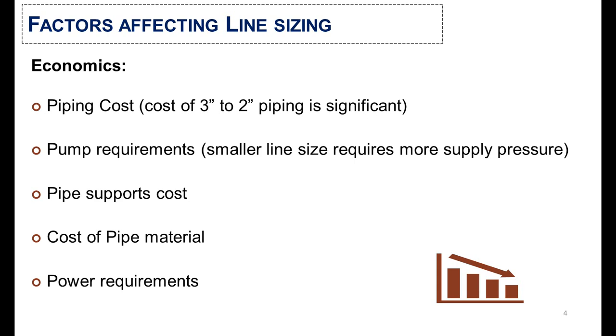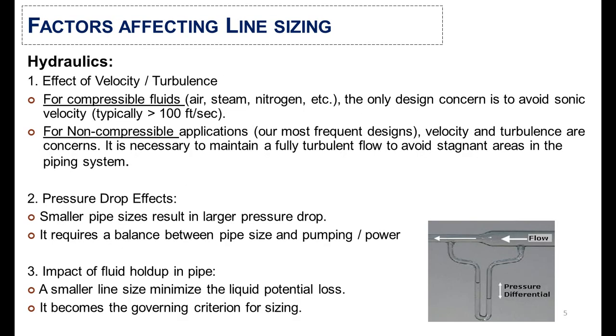The last economic factor is pipe power requirements. In hydraulics, the first consideration is the effect of velocity and turbulence. For compressible fluids — for example, air, steam, and nitrogen — the only design concern is to avoid sonic velocity, which is typically greater than 100 feet per second. For non-compressible applications, which are mostly used in designs, velocity and turbulence are concerns, and it is necessary to maintain fully turbulent flow.